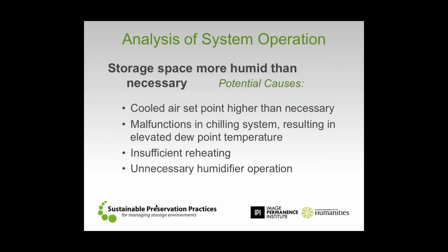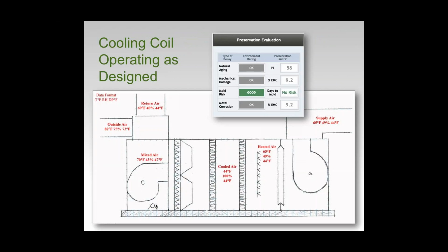If we've got high RH, too much humidity, watch the cooled air set point, make sure that the cooling coil is dehumidifying as well as it can. Make sure that you're doing enough reheat. Here's a key right here, and just to walk through these real fast, this is a cooling coil that's doing what it should, right? We have cooled air getting down to 44 degrees to give us our 44 degree dew point, sent out to the space. We wind up with a PI 58, and all of our preservation conditions look really good.